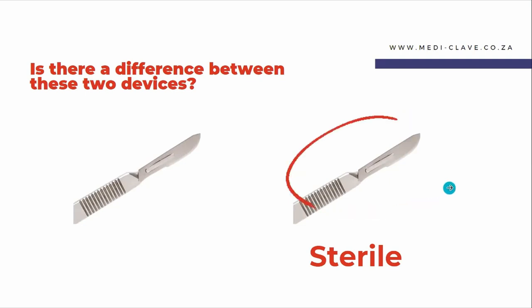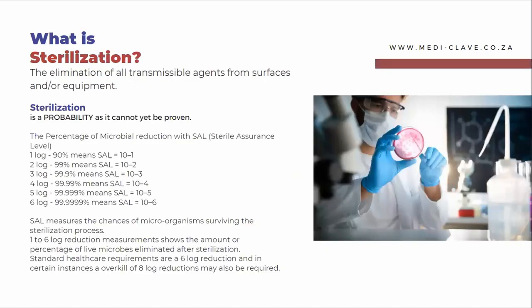So let's go into a little bit more detail. What is sterilization? Sterilization is the elimination of all transmissible agents from surfaces and/or equipment. Alternatively, as I like to refer to it, the battle against the bugs. Sterilization is a probability as it cannot yet be proven. So sterility assurance level measures the chance of microorganisms surviving the sterilization process as a 1-to-6 log reduction. That shows the percentage of live microbes eliminated after sterilization. The standard healthcare requirement is a 6 log reduction, and sometimes an overkill of an 8 log reduction is also required.